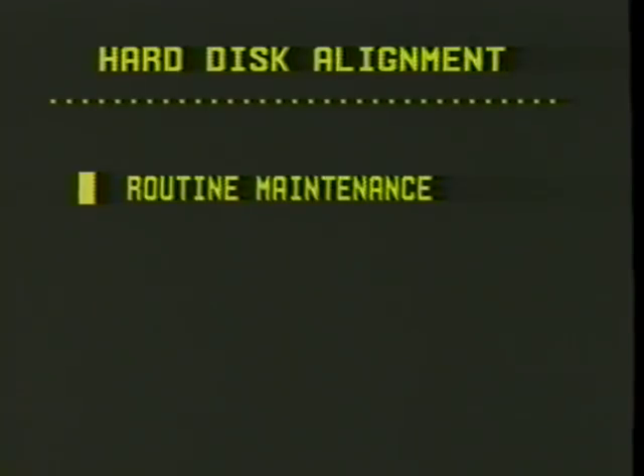Finally, some designs allow the technician to adjust the error amplifier's output for a minimum number of corrections during operation. There are several situations in which we must perform these adjustment procedures. We need to check the alignment during routine computer maintenance. If we correct misalignment early, we may prevent loss of customer data.